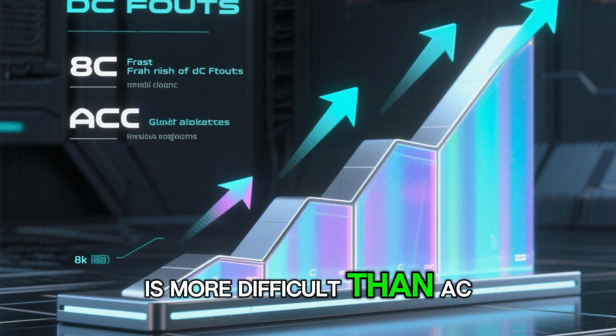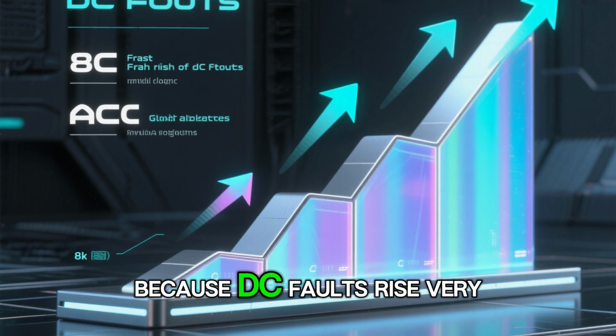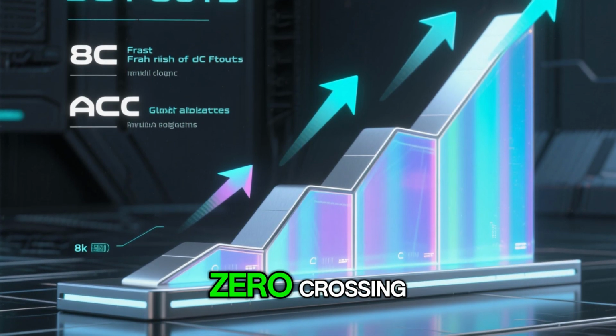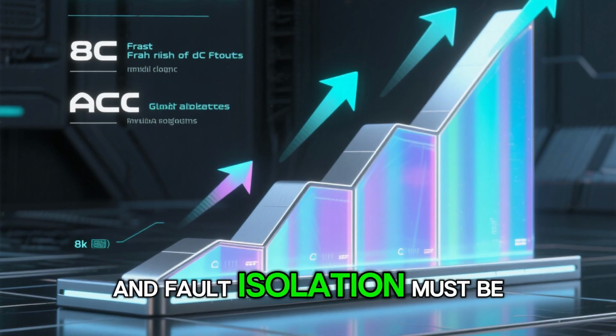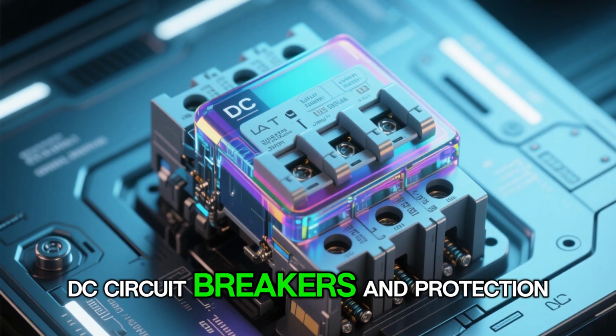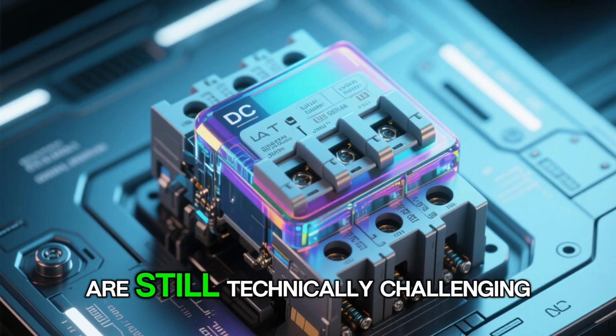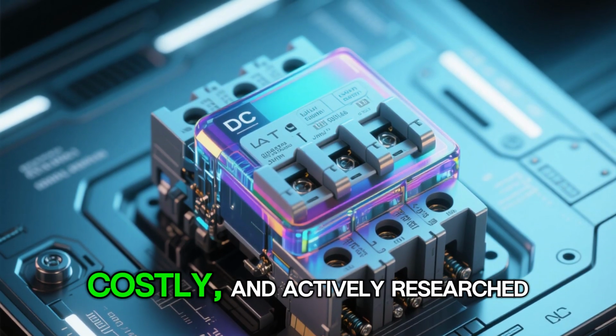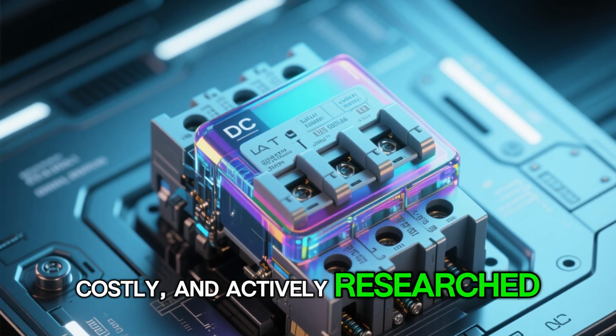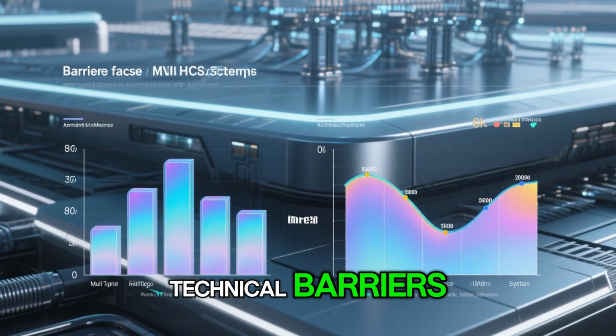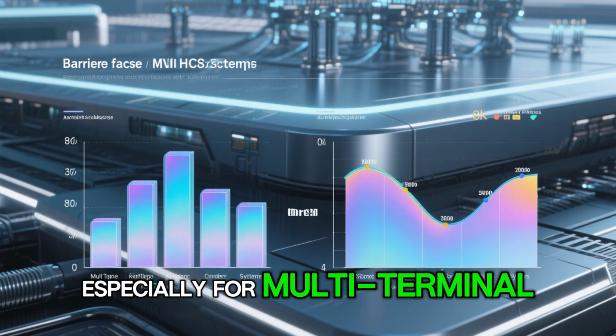Protecting HVDC systems is more difficult than AC systems because DC faults rise very fast, there is no natural current zero crossing, and fault isolation must be extremely fast. DC circuit breakers and protection algorithms are still technically challenging, costly, and actively researched. This remains one of the biggest technical barriers, especially for multi-terminal HVDC systems.